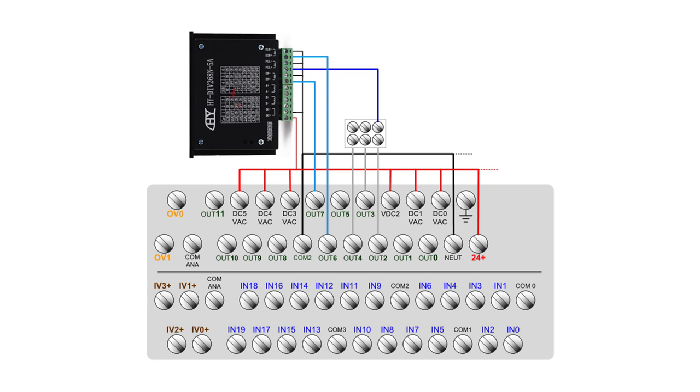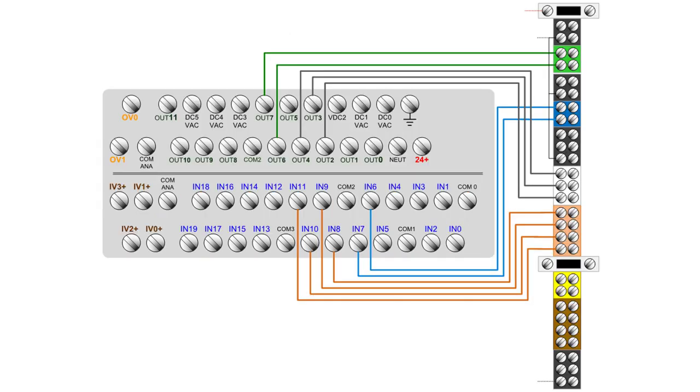And remember that these high-speed counter functions are specific to certain input terminals, because if you can use a high-speed counter on one of these inputs, it has its own special electronics built into each of those inputs that do the high-speed counting that would get missed by a normal input scan from your controller.